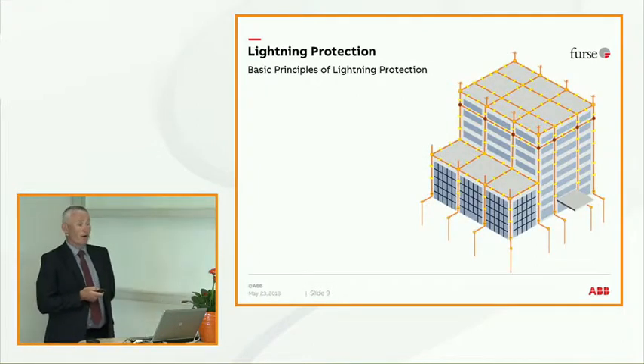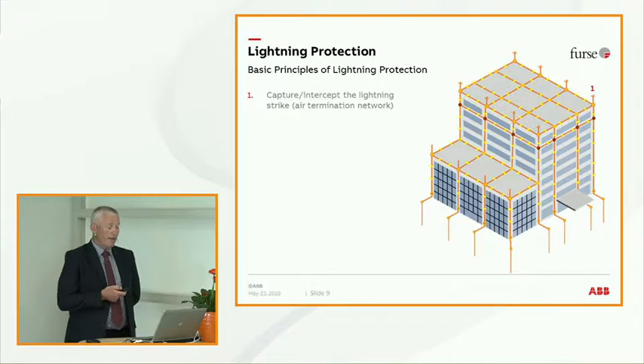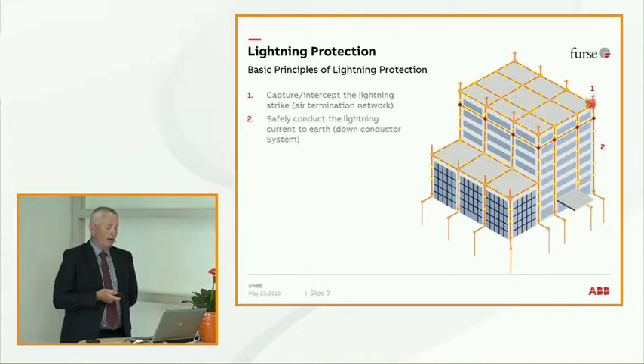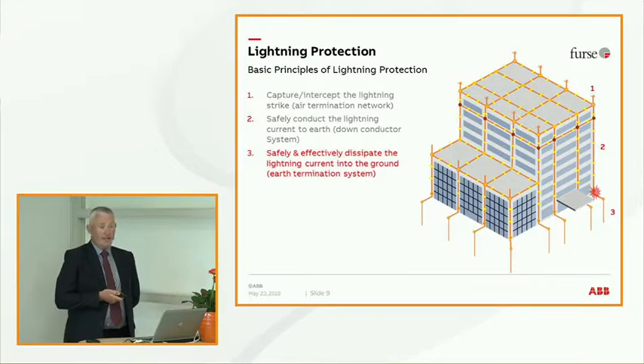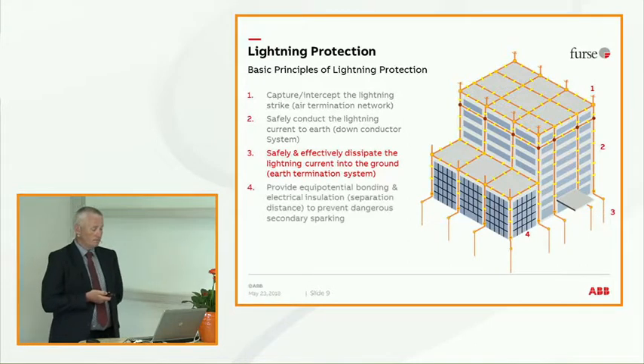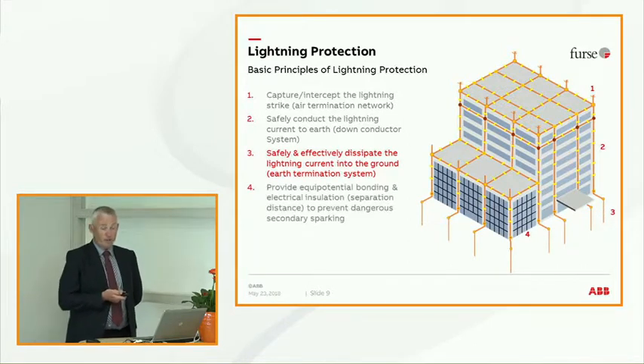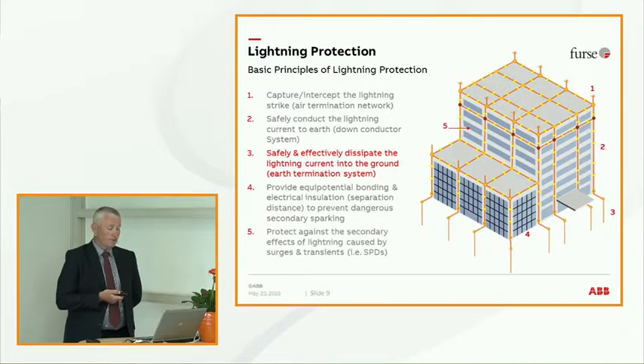The basic principles of lightning protection, I'm sure most of you are aware, are to capture and intercept the lightning strike at the air termination network, safely conduct the lightning strike to Earth, and then dissipate it into the earthing system. And then, like I said, it's to provide the equipotential bonding. There's also the requirement to protect against the secondary effects of lightning, which my colleague from ABB will be talking about shortly.